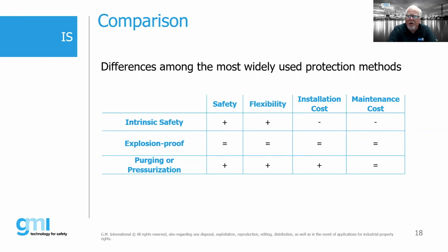Now, again, these are somewhat generalities. Everybody's application is going to be different. But typically, if we're talking flame proof or explosion proof, for power cables we're going to use some sort of armored cable. We might have flexible conduit or rigid conduit. In some cases we're going to have barrier glands. With intrinsic safety, because everything beyond the IS barrier is in effect safe, we can do things with our cabling and glanding that are not necessarily the same as the installation details we would use on a flame-proof installation. So again, it depends on the markets you're in and on the standards you're following.